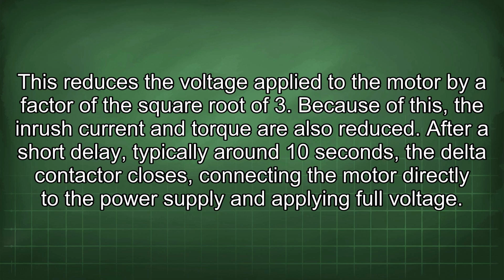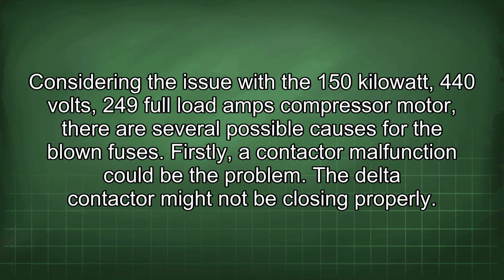After a short delay, typically around 10 seconds, the delta contactor closes, connecting the motor directly to the power supply and applying full voltage. Considering the issue with the 150 kilowatt, 440 volts, 249 full load amps compressor motor, there are several possible causes for the blown fuses.